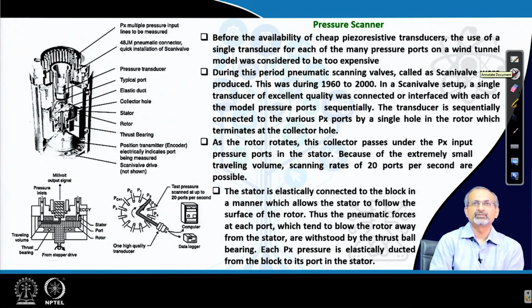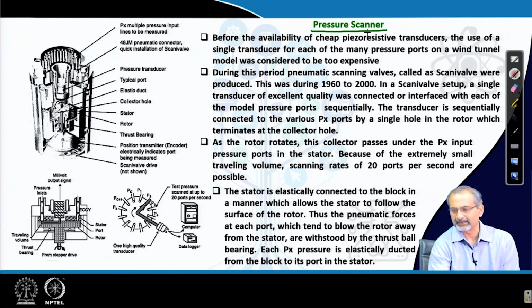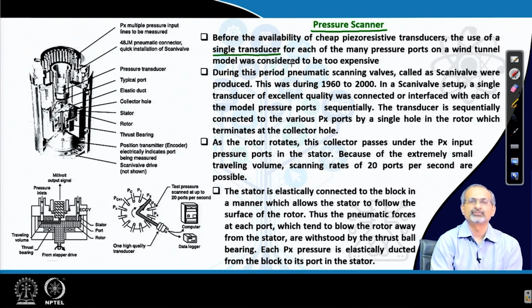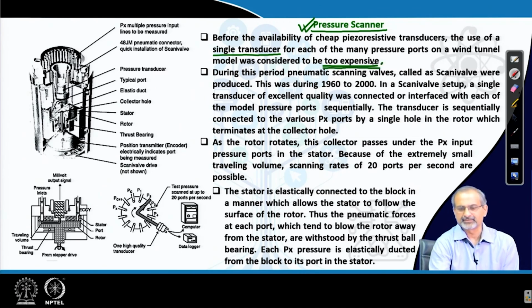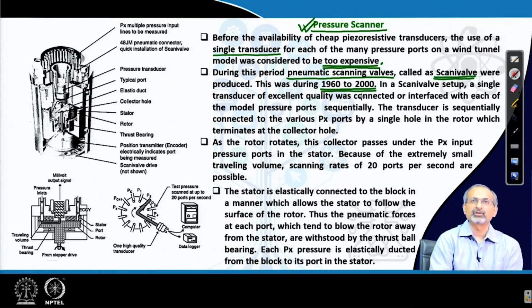Let us look at a very interesting configuration which has remained in service for long in this electronic pressure measurement world, which is basically the concept of pressure scanner. These days piezoresistive transducers have become much cheaper, much more affordable, but there was a time when they were extremely expensive. So, at that time the strategy was to use a single pressure transducer to measure pressure from many ports of a model mounted in the wind tunnel. This was possible through a pressure scanning or pressure scanner system. This was primarily a constraint due to the expense. During this period, pneumatic scanning valves called scanivalves were produced, and they were very popular for a long period of about 40-50 years.